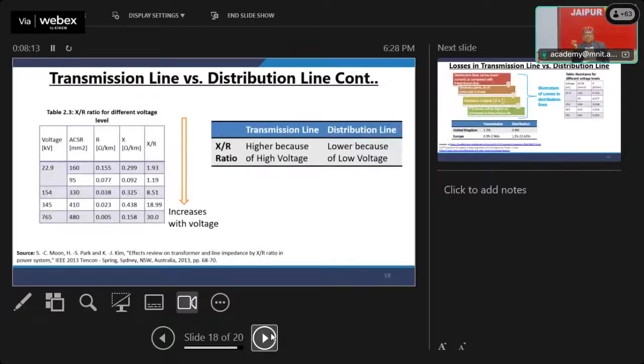Okay, next please. This is a very, very important slide. I request everyone to pay attention. This slide is almost my favorite in one sense. I mean the R by X ratio or X by R ratio, which is slightly different in transmission and distribution lines. So the X by R ratio is higher in high voltage transmission lines. However, it is lower in distribution lines. If you see the voltage level, the way it increases from 22 kV to 765 kV, the X by R ratio keeps on increasing from 1.93 to 30.